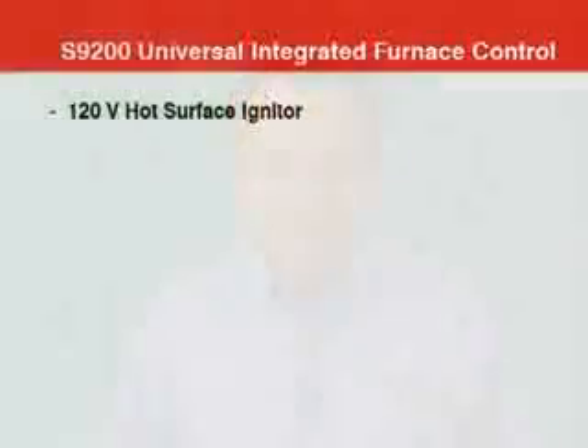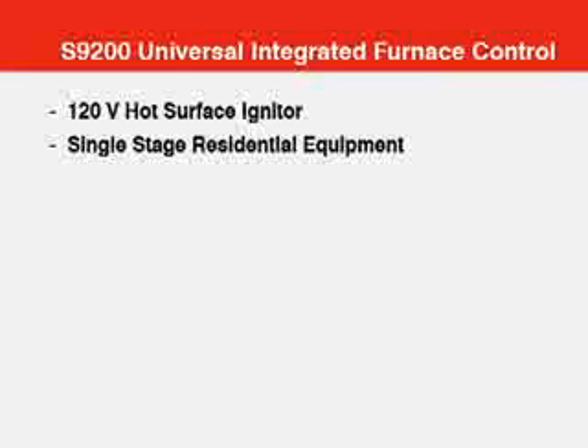We've all seen the benefit of stocking universal replacements such as Honeywell's Tradeline and Super Tradeline gas valves and electronic ignition modules. You've always got the parts you need to get a system up and running on your first trip to the job. Now you can expect to get some of those same benefits when dealing with furnace controls. Let's get to specifics. It controls a line voltage hot surface igniter to directly light the main burner in a gas furnace or other gas-fired heating appliance originally designed for an integrated furnace control. It works with single-stage heating and cooling and either natural or LP gas systems.